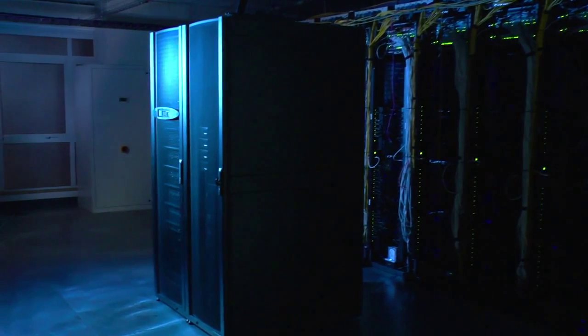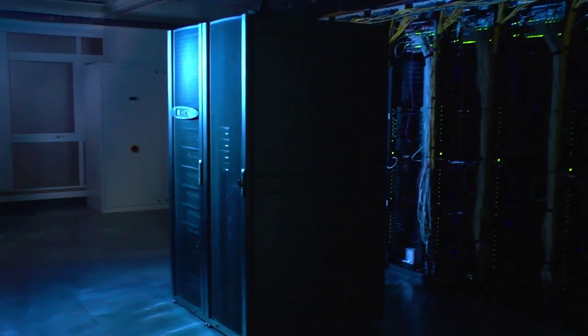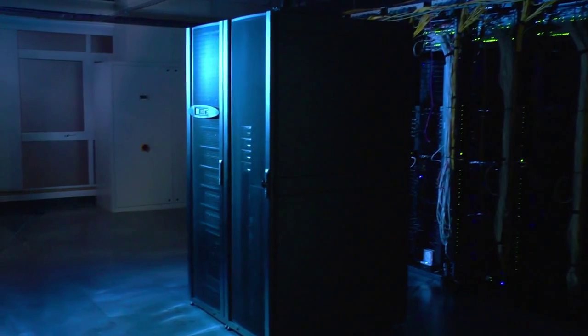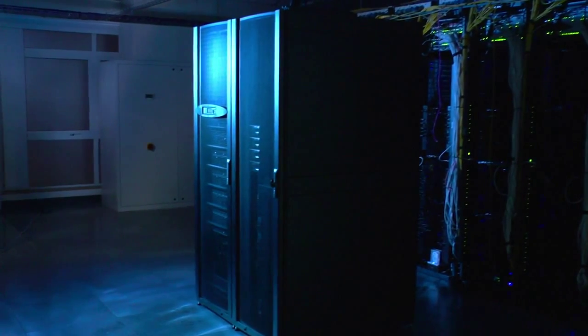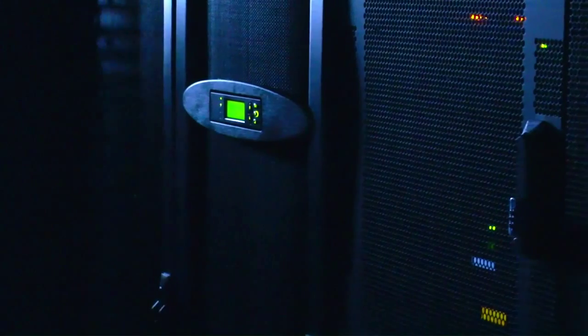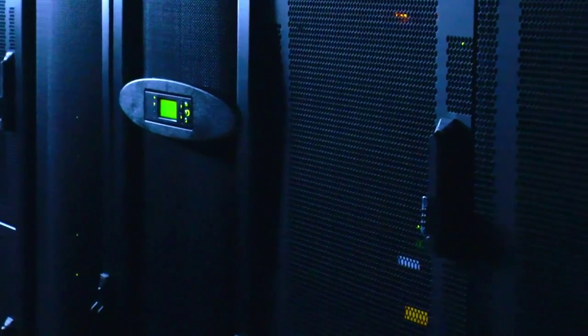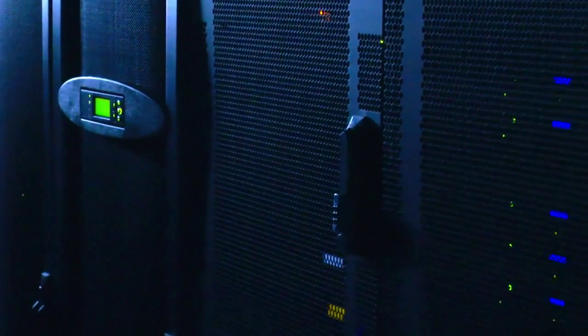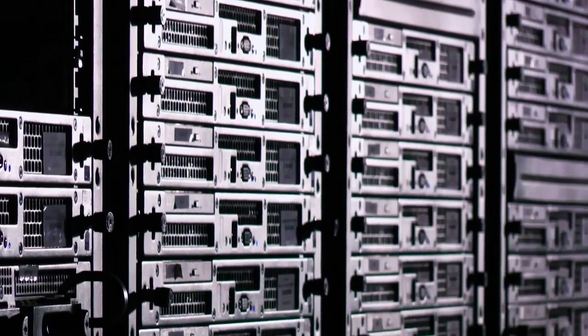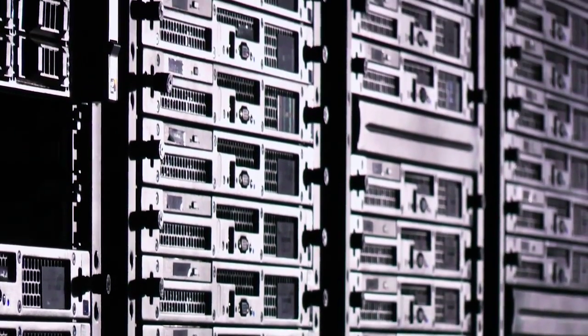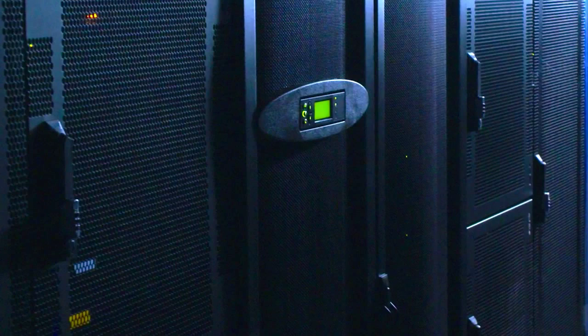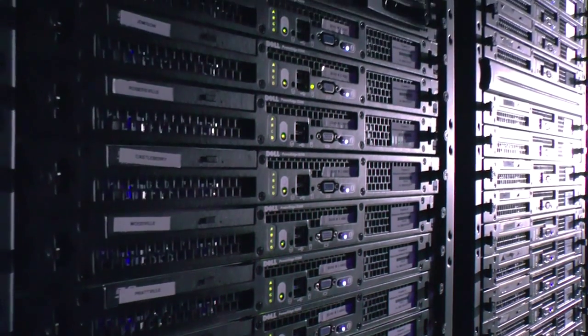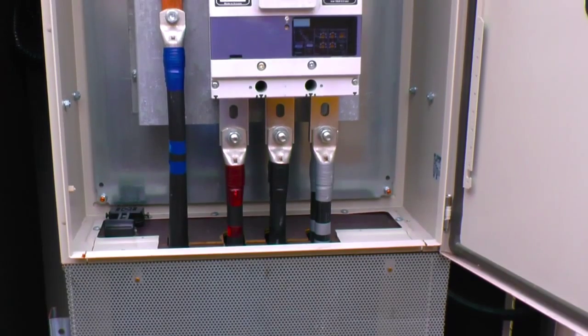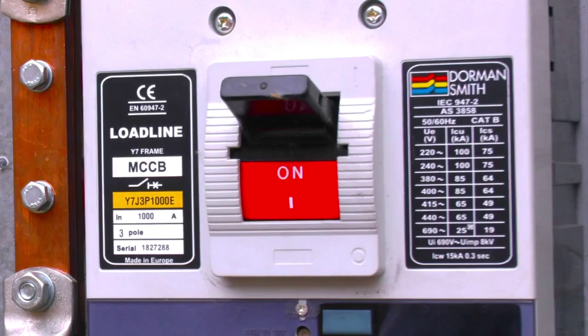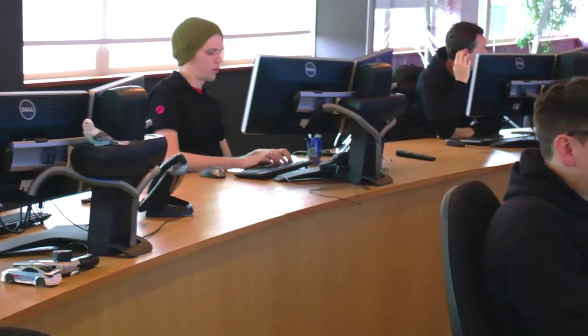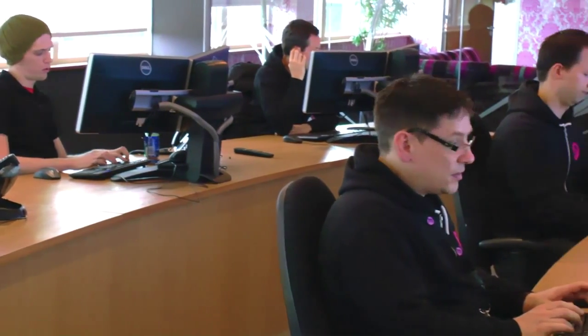We have opted to have a modular UPS system rather than a single plant, so there's no single point of failure for the entire facility. Each UPS has hot swap batteries, and any critical component has an online spare that it can seamlessly and instantly switch over to. You have the option to have multiple feeds in your racks, and these can come from different UPSs, therefore giving you a much greater resilience. Importantly, every month we cut the power under controlled circumstances to prove that our multi-layered power plan works.